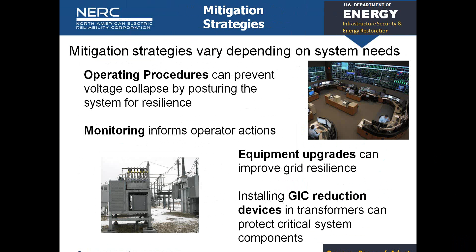So you can zoom back to my slide — I think it was slide 9 — on protection. A GIC blocker is certainly one way to protect, because this current goes into the transformer, and Mark went over the different things it can do: it can cause voltage collapse, it can cause overheating of the transformer. You can just block that current from coming in through the neutral. The GIC blockers on the market today are basically like a capacitor, which blocks the current from coming in.